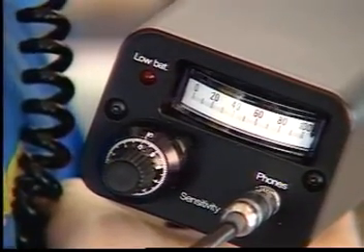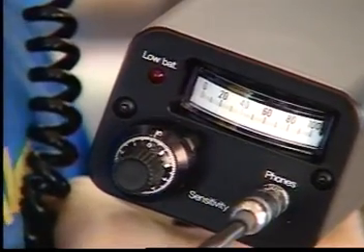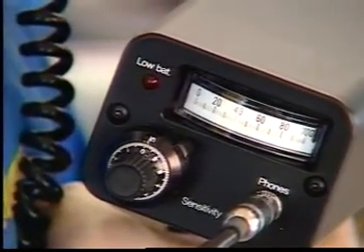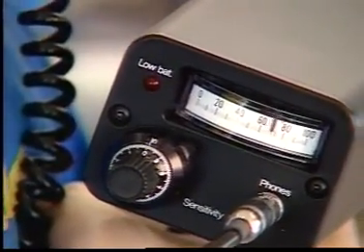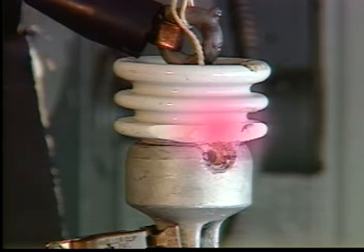This is the actual sound of destructive high-voltage corona at a severe stage. Listen to the sizzling sound. This is the sound of tracking over the surface of a cracked insulator. Whereas corona is found at points where electrons jump off into the air, with tracking you'll be able to follow the sound of the electrons running along a damaged site.